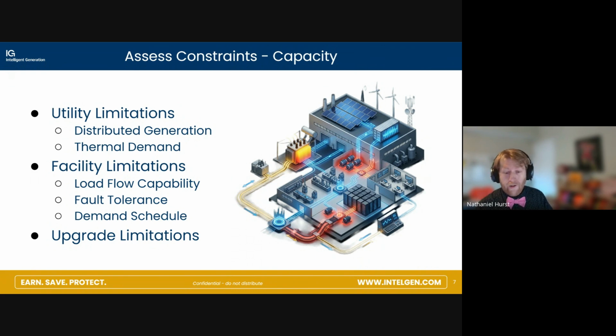If you want something more sophisticated, that breaker might have some level of intelligent control. The NEC, UL, and IEEE are all now recognizing power control systems as a legitimate means and method for controlling current. Many batteries have these functions built in, but as the site gets more complicated, with more variables on the customer side, this becomes a system you have to design from a top-level master view topology.